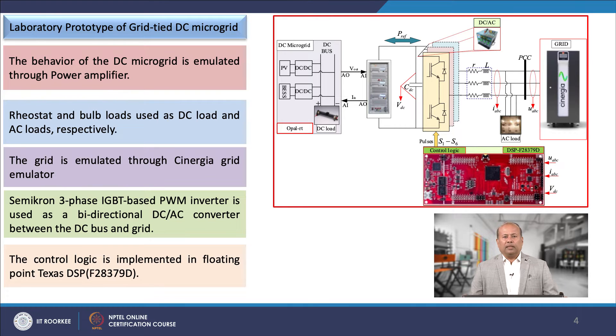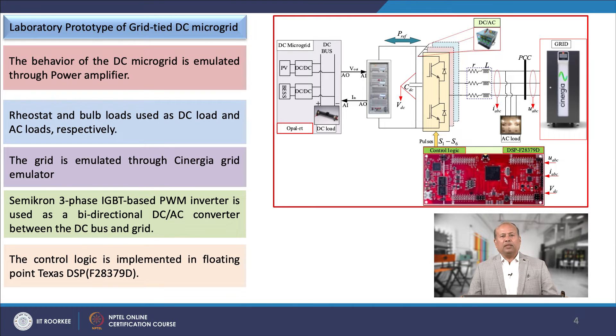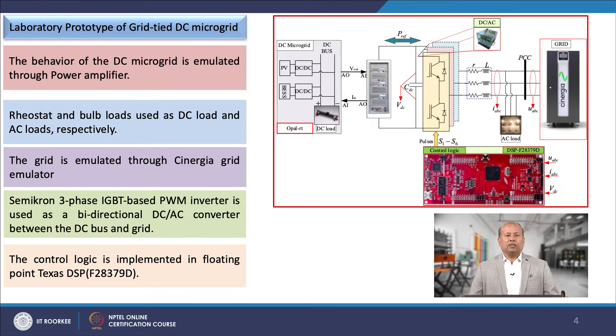The behavior of the AC grid is mimicked through a Cinergia programmable grid emulator. A Semikron three-phase IGBT-based PWM inverter is used as a bidirectional DC-AC converter between the DC bus and the grid. The control logic shown in the previous slide is implemented in the DSP controller — the floating point Texas C2000 DSP controller of the TMS320F28379D Delfino type.